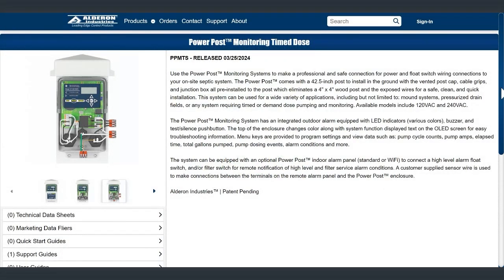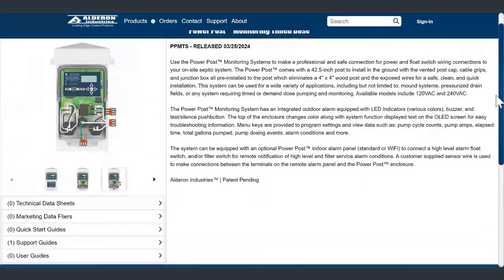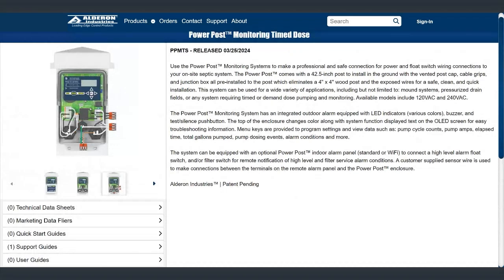And I don't want to get too far into this because the PowerPoint's going to go over a lot of that. But yeah, so if you're using it for a demand dose system, you can do the piggyback or the control circuit. And in time dose, you have to use the control switches, which are more cost effective. But then if you want that redundant off float, that is a piggyback pump float, because the full load amps have to go through that. All right.